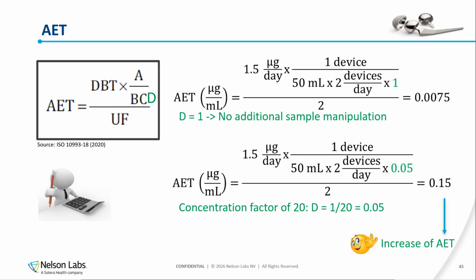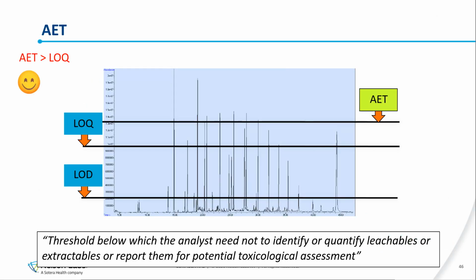Now to the next line, I have changed only the concentration factor. Instead of 1 or no concentration, I increased it to 20. 1 divided by 20 is 0.05. And we see an increase in the AET, which is good. And why is this good? Well, for any organic screening method, there is a limitation in the instrument and the methodology. It's called the limit of quantification and the limit of detection. These are the limits of the instruments. And if your AET is above that, everything is fine. You are able to reach the AET with your limits, let's say.